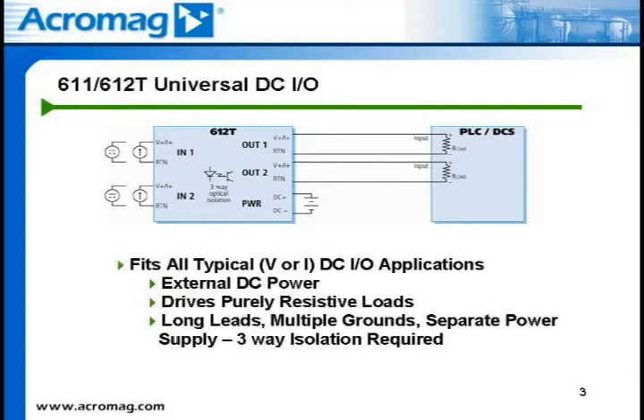Also, the external power supply does not have to be a regulated power supply, as it will work off a range of 10 to 36 volts DC. Typical applications would be if you want to add another load, such as a chart recorder, or a display, or a PLC input, and power needs to be isolated. You can install the 611T or 612T to drive the extra load.